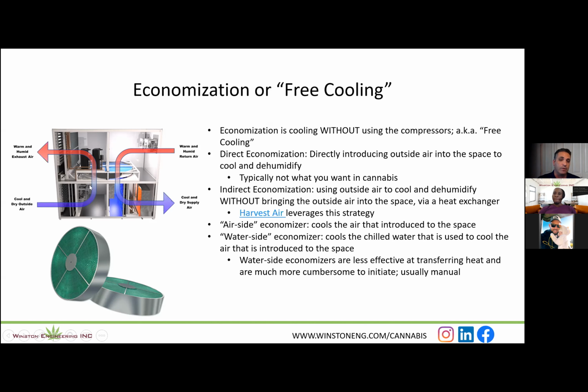So effectively, that wheel does nothing but rotate between those air streams, exchanging heat and humidity. It's about 85% effective at rejecting heat, so you don't get the full benefit of the outside air. But when you're using that wheel, guess what you're not using? The compressors. And that's how you're saving lots of energy. So air side economizers, that's effectively what we're looking at here.